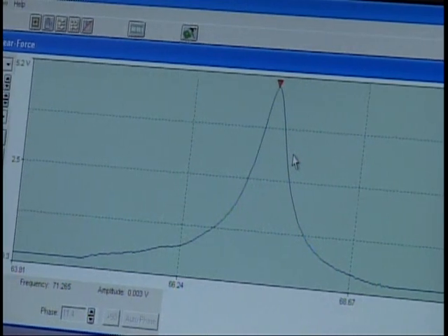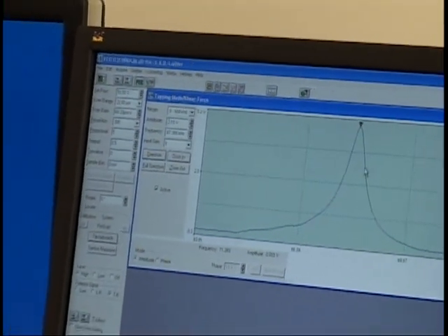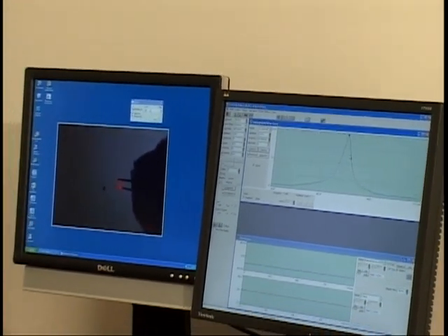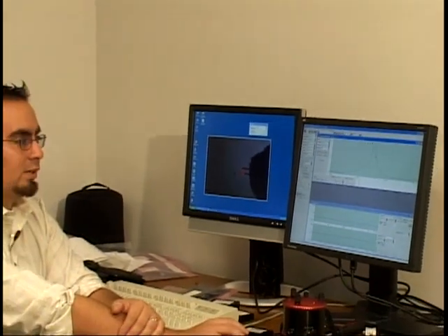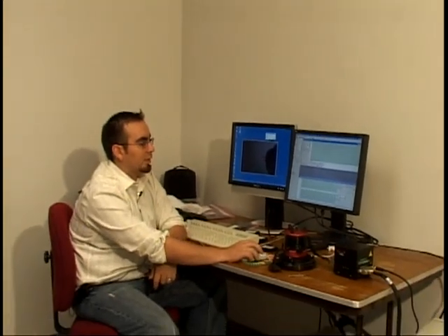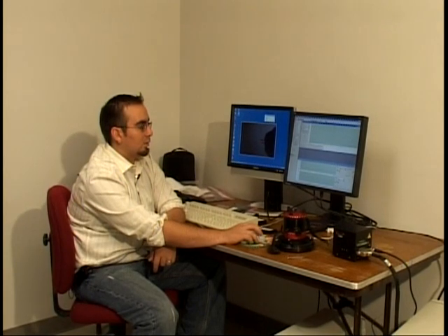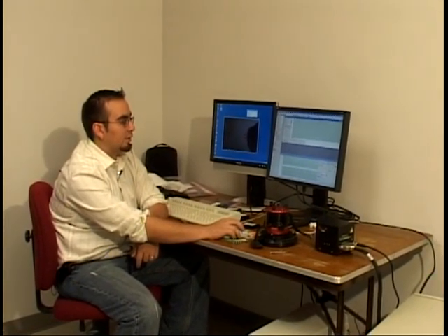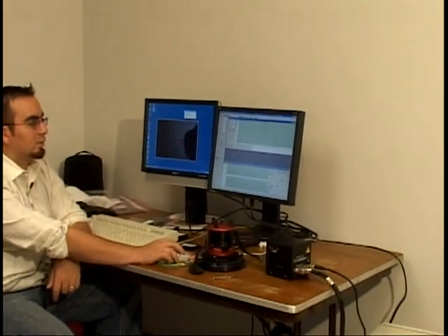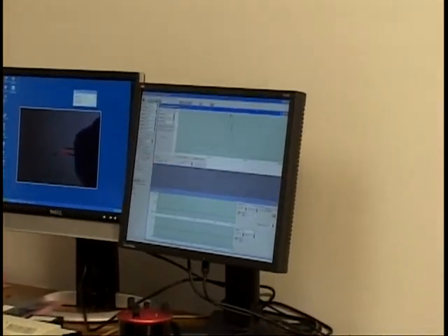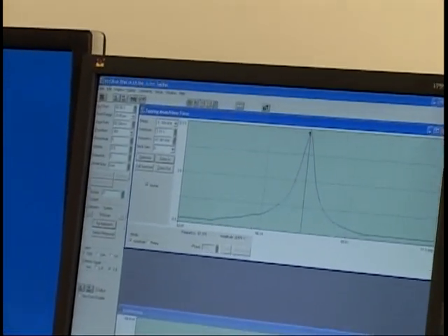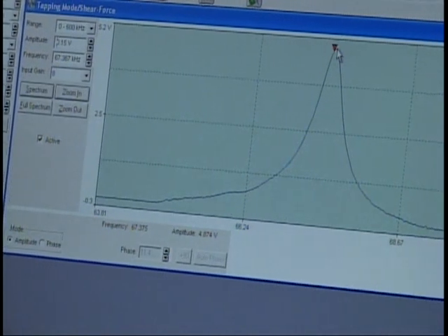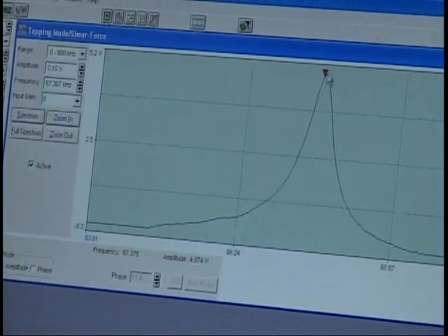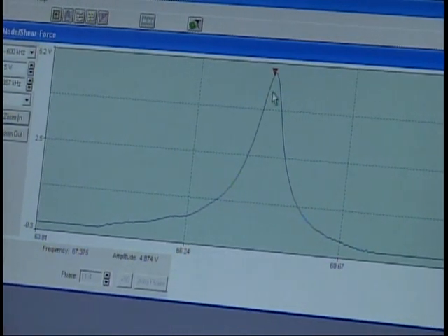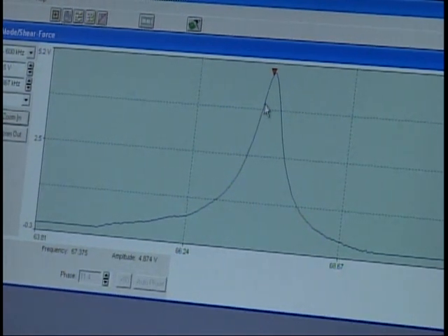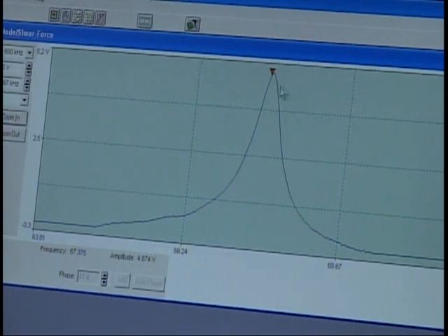That might be a sign of something on the probe that's hanging on, or a damaged probe, or maybe it's not even mounted right, or you don't have a good sum on it, or aligned right. So right now we're reading, let's see, we'll left click on the peak and the red crosshair will appear, or select our amplitude, and that should be giving us a reading. So right now we're looking at 4.874. And when you choose your frequency, try to choose a little bit to the left of the peak, so don't do the apex of it. Go a little bit to the left of it, because once you engage, it will dampen out the natural frequency, so it'll do a little shift to the left. So you want to catch that before you engage.